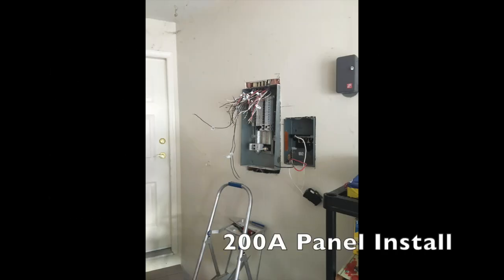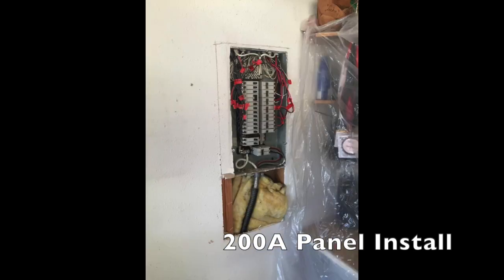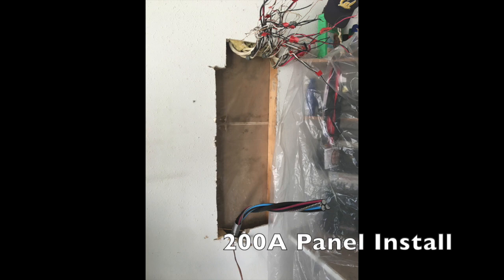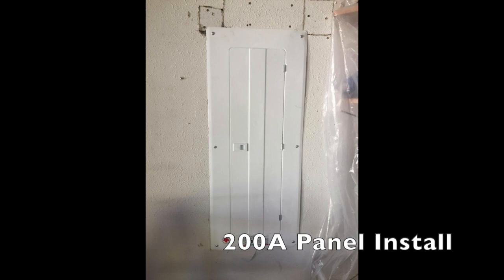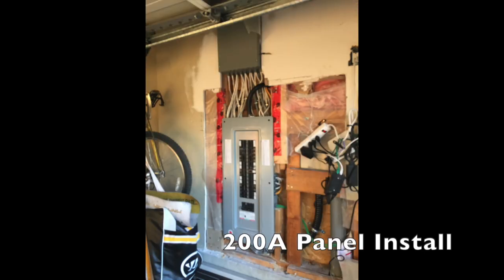Okay, next we're going to go inside into where your electrical panel is installed. Your current one is most likely going to be a 100 amp panel or a 125 amp panel. It varies depending on your house and what the original install was, but right off the bat we tell customers that drywall will have to be removed. As an electrical contractor, we only perform electrical work. We do not repair drywall after it has been damaged. As you see in this current image, there's a junction box above the electrical panel.